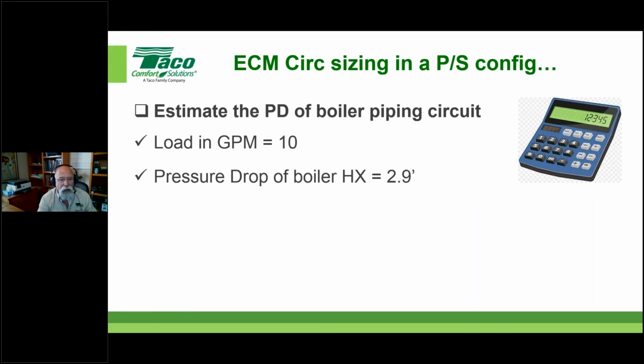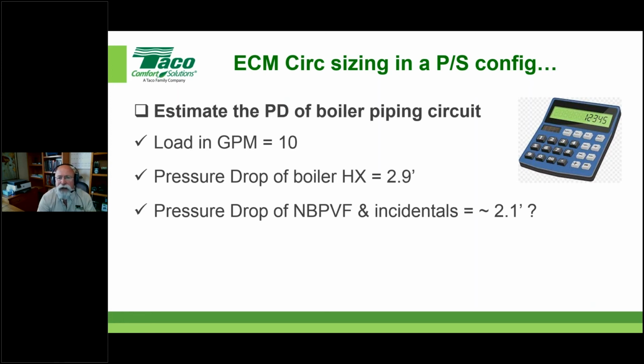And again, a lot of these manuals, if it has to be from somebody else that has a similar one, you could probably use that. In this case, I'm just under 3 foot of head. As long as that boiler manufacturer did not add for the incidental pipe, valves and fittings, then you're going to have to add for that slightly. But when it's appropriately sized and relatively short, like most of the near boiler piping is on the primary side of a primary-secondary configuration, then it's usually a foot or 2 foot of head, maximum. So again, we take things into consideration like, is there a magnetic dirt separator on there? Are there balancing valves that somebody has cut in there? That sort of thing. That all has to be considered in that estimate.